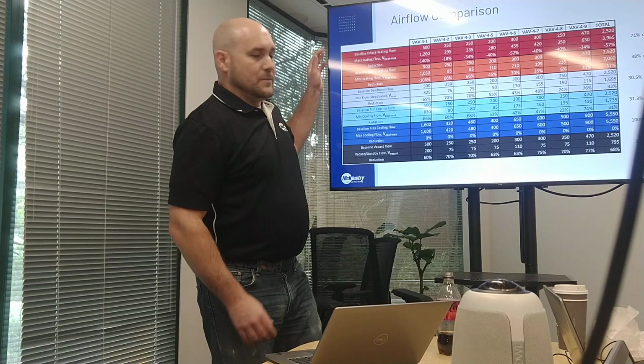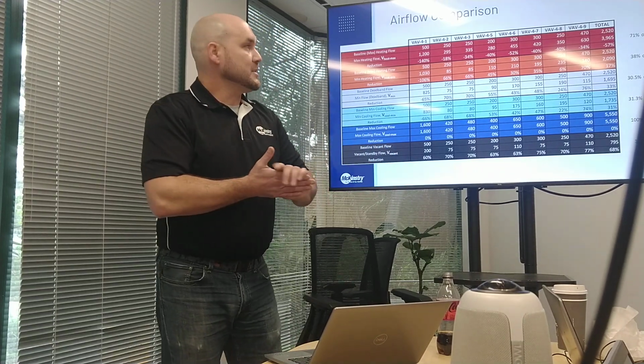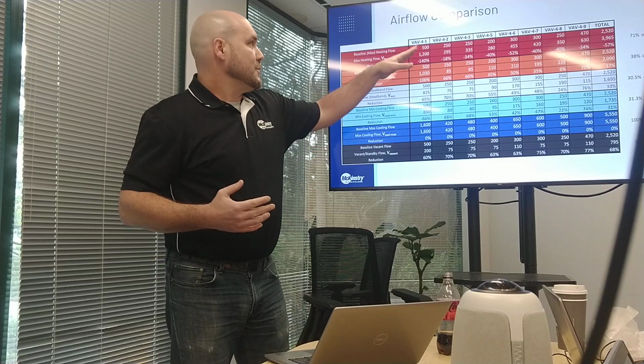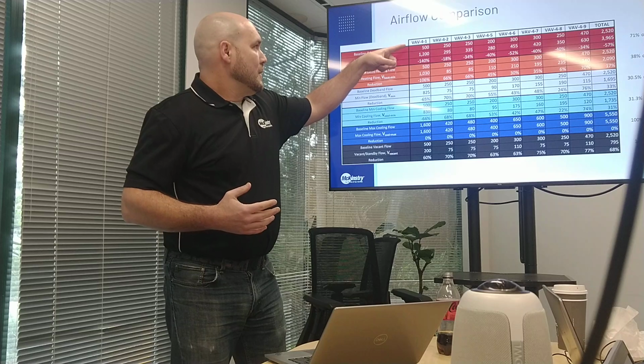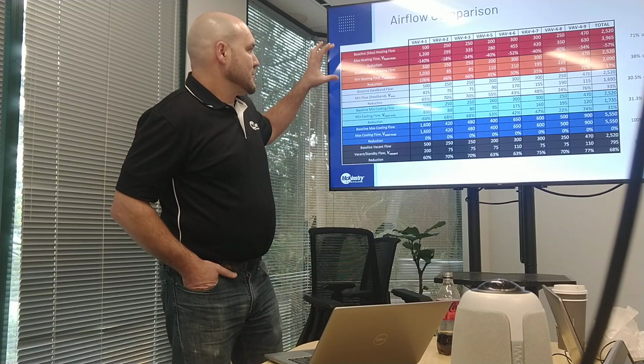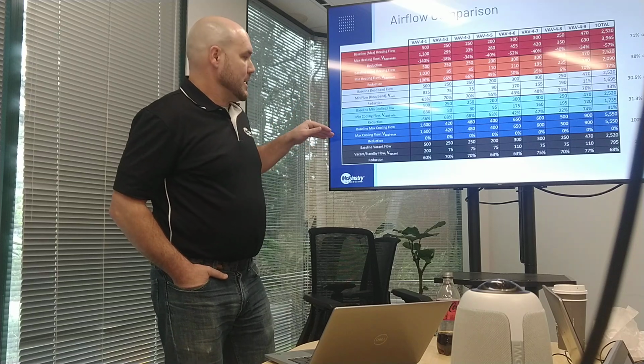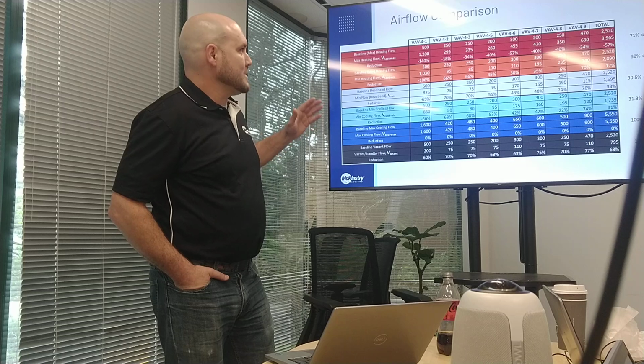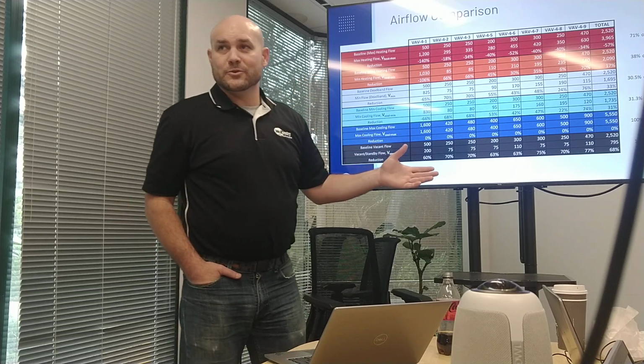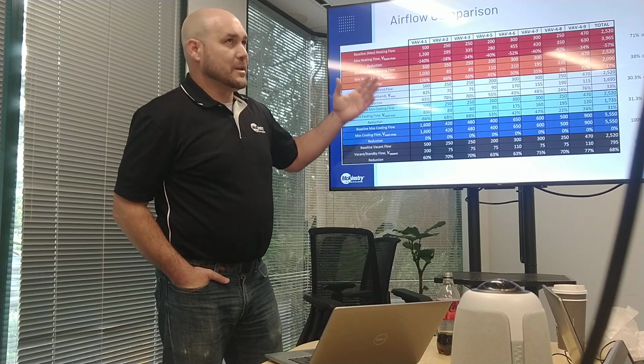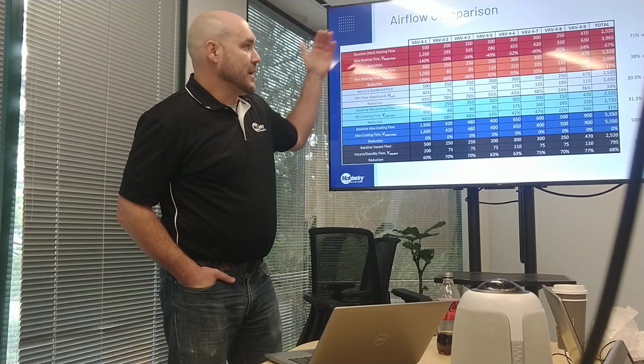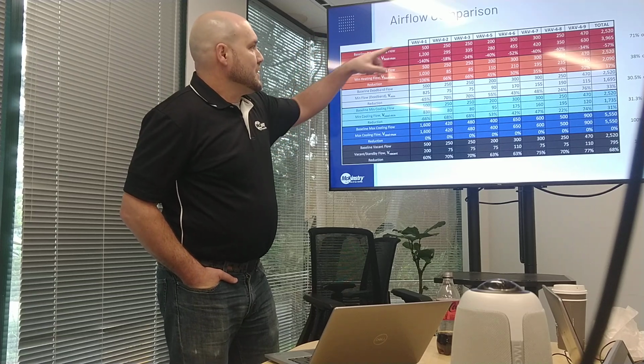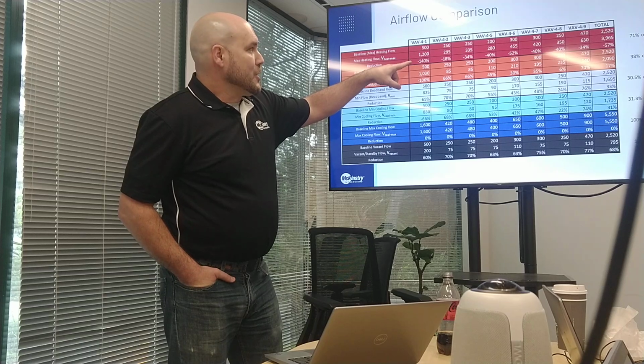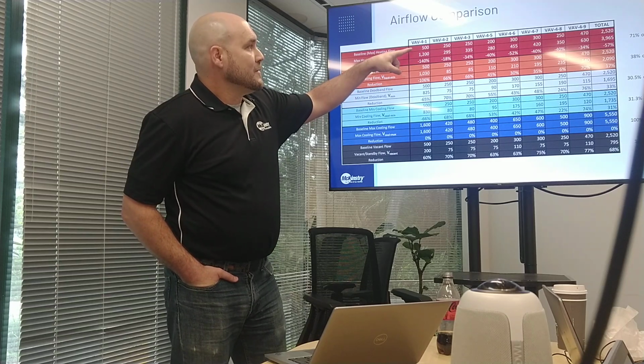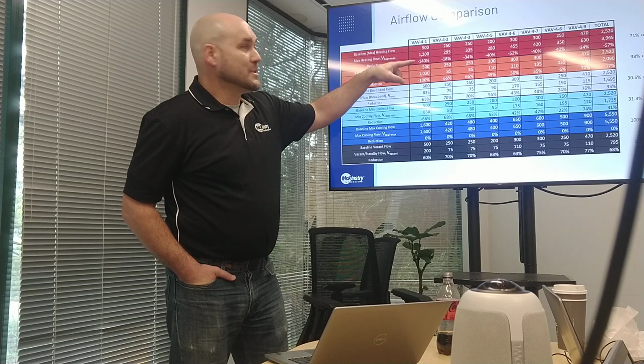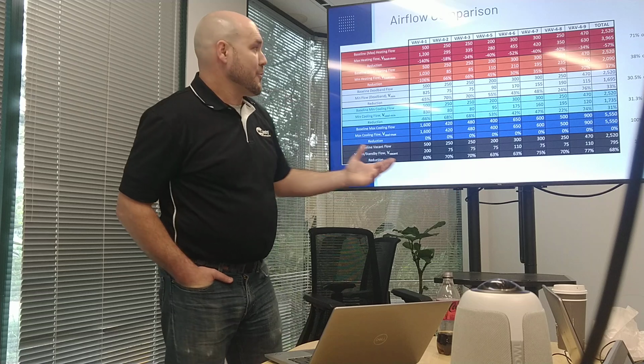So yeah, just going through these, what were the airflows of this system when we found them? So the baseline value, for this first one, heating airflow was 500, and so these are the different scenarios that Guideline 36 has, but it was using one of the old school methods. So if it's heating, whether it's minimum or maximum, it was still using its 500 CFM value. So what you'll see for this VAV box number 1 is that we're going up in airflow, yes, from a minimum of 500, what it used to be, to 1200. The difference is we're ventilating properly and they weren't ventilating properly.